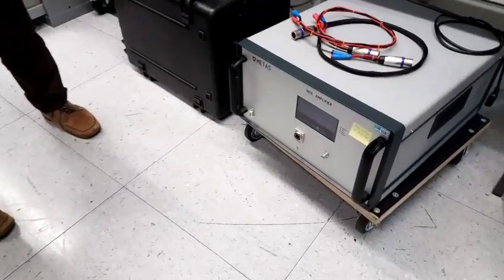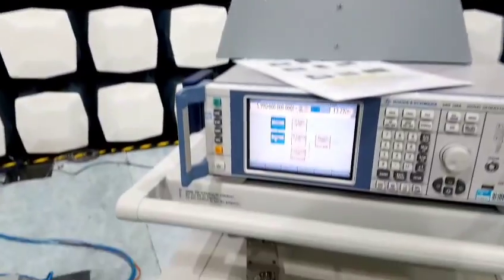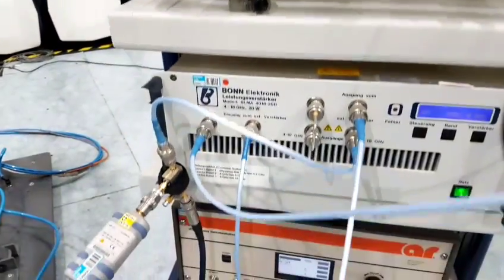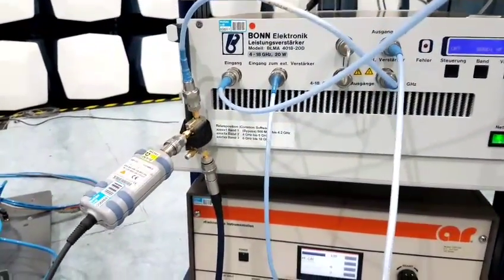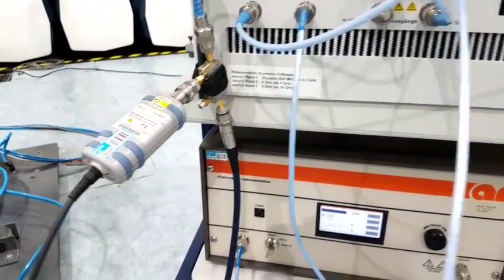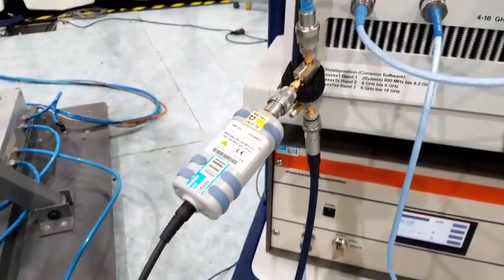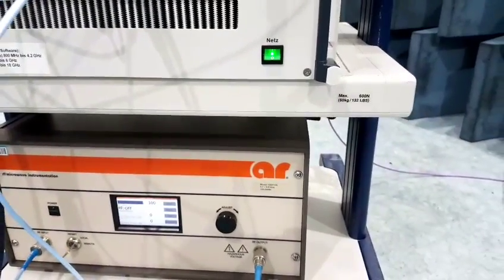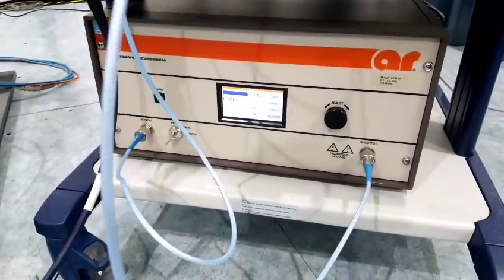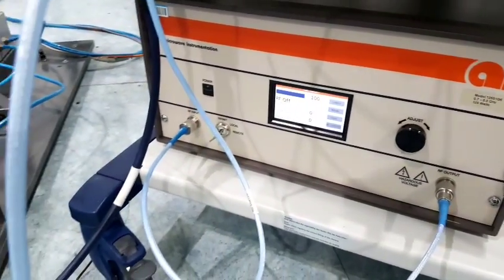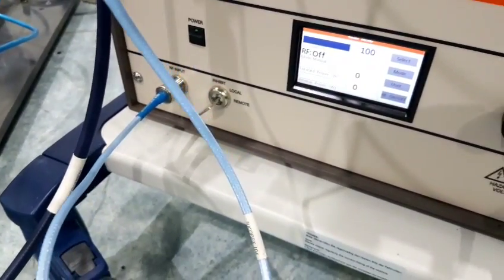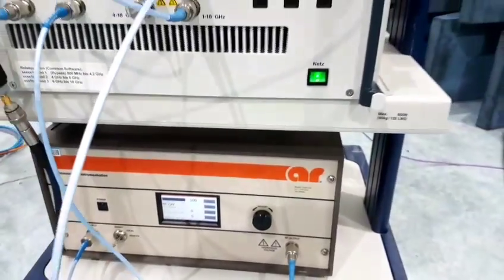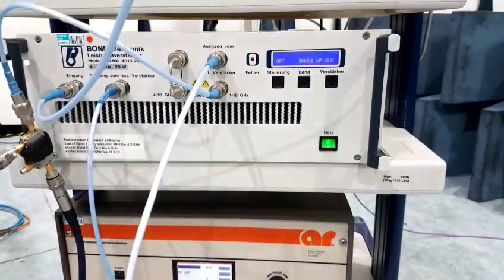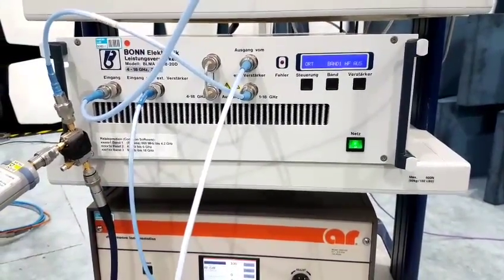We check the linearity, frequency response, and everything in this range. We can calibrate field probes from basically 10 hertz to 18 gigahertz, checking isotropy, linearity, and frequency response.